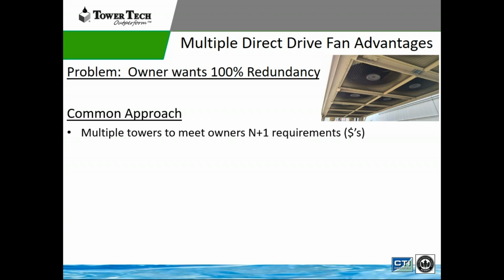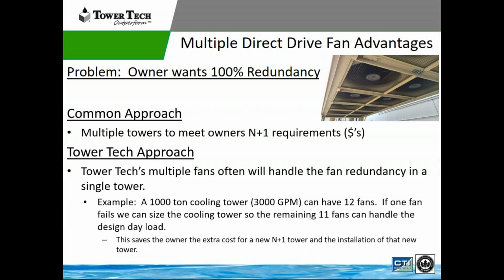However, that's expensive from a piping standpoint, install standpoint, material standpoint, control standpoint, everything standpoint. On the Tower Tech side of it, we have multiple direct drive fans. On a traditional 1,000-ton chiller plant, say 3,000 GPM, we can offer a 12-fan system. That's the largest fan system. If one fan fails, we can assure that we can operate that load with 11 fans on that system. This saves the owner an extra cooling tower footprint and the controls associated with installing an additional tower. So this is a great approach when we talk about the redundancy of the Tower Tech system.